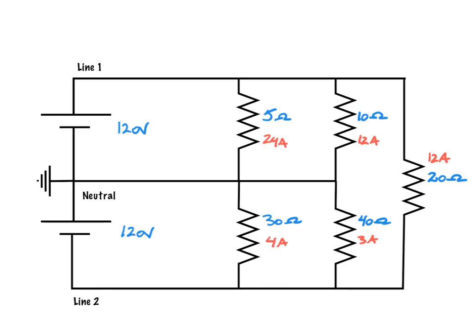Now we can determine our line currents based off of these. Now if I'm looking up here, and by up here I mean up at line 1, you can see that we have this branch where current is coming up across it at 12 amps, gets to this node, and it picks up another 12 amps, so it ends up being 24 amps, and kicks it over to this node, and picks up an additional 24 amps. So in total, we can say that this line here has 48 amps.